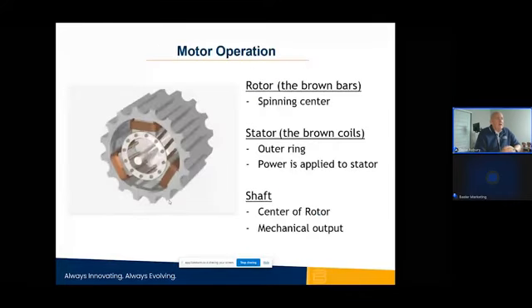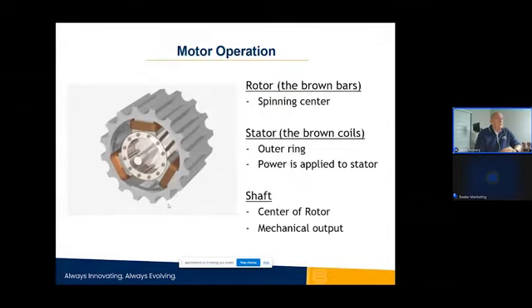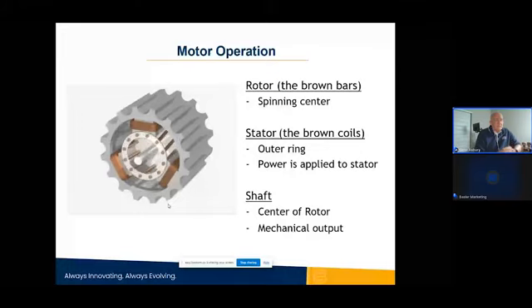So this kind of illustrates what each part is actually doing. The spinning center, the rotor, is interacting with the squirrel cage winding and the RMF that's being developed from the power supply to the stator windings. So as the rotor is spinning and it locks into synchronism, the outside excitation supply that is being applied to the field winding is going to create that flux, or the energy needed to keep that in synchronous speed.